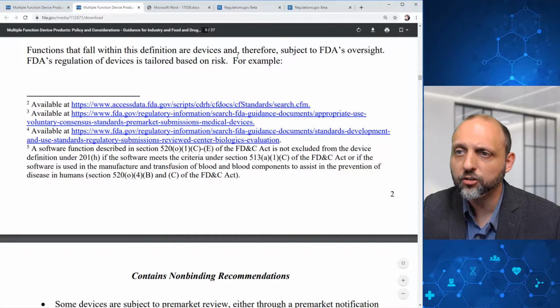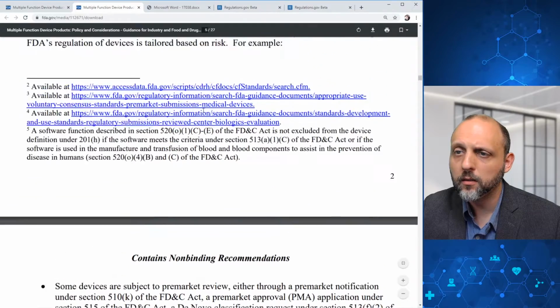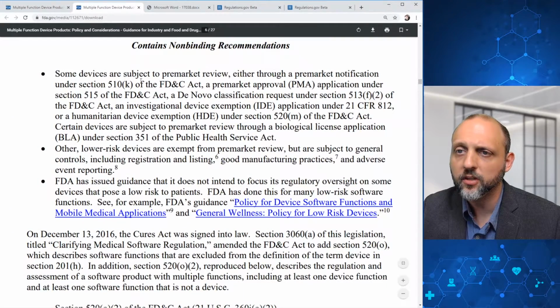Functions that fall within this definition are devices, as we noted, subject to FDA's oversight. And for example, FDA notes that some devices are subject to pre-market review. That would be PMA submissions, may require de novo classification, an investigational device exemption, a humanitarian device exemption. This IDE would be a clinical study. HDE would be a narrower subset of the population of, let's say, a PMA device. This would be limited to a smaller number of patients annually who could experience the condition, which would be a requirement for HDE amongst others, or a BLA.